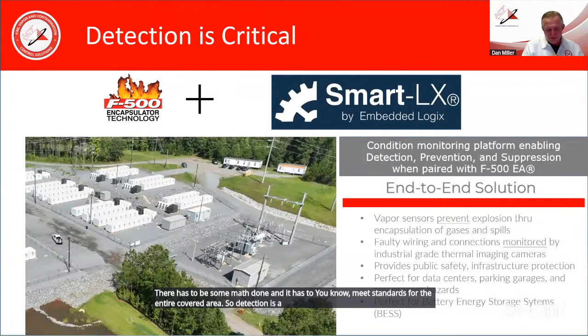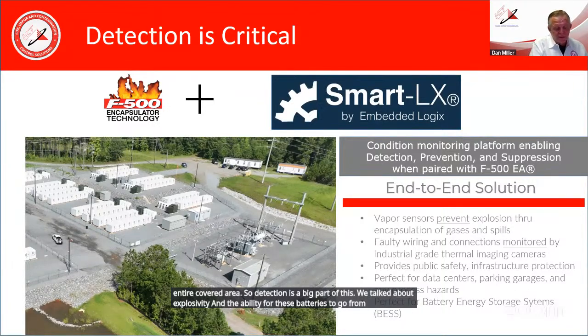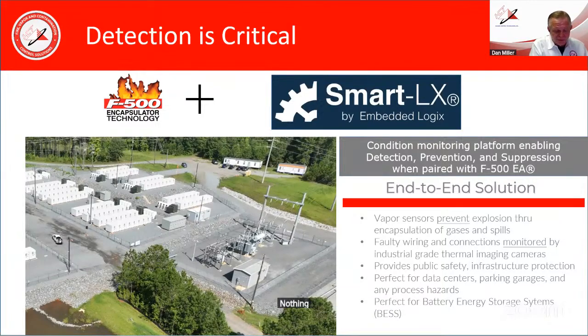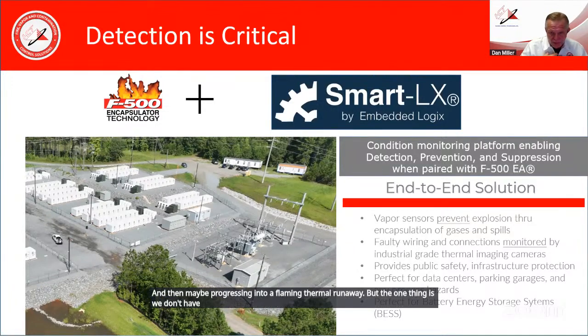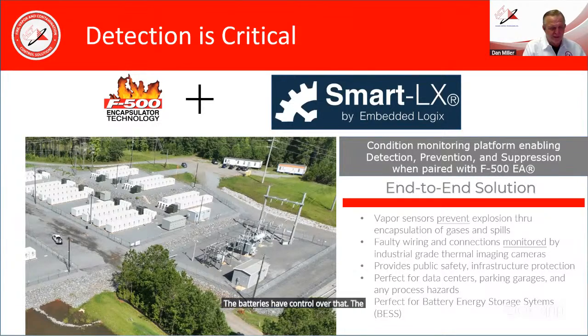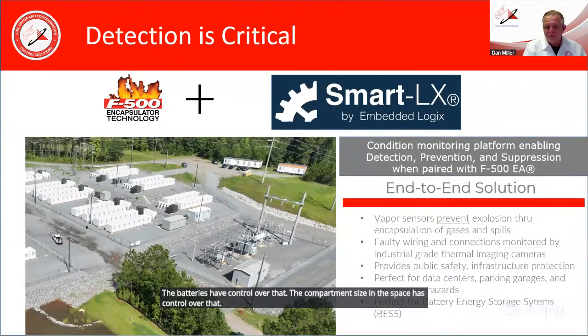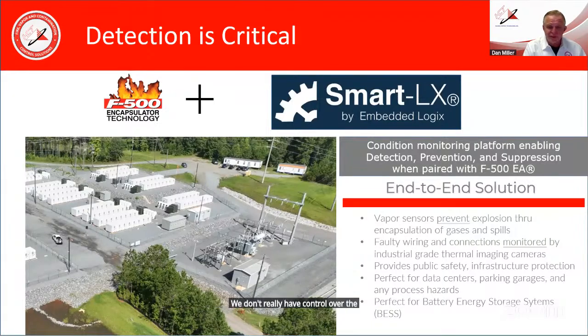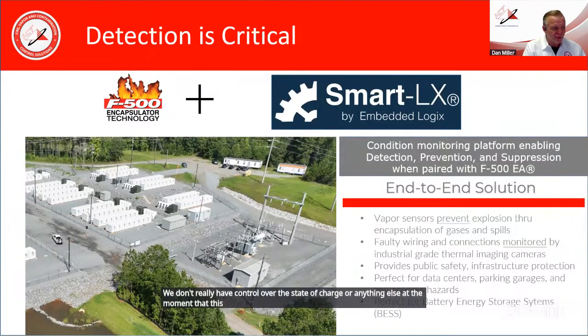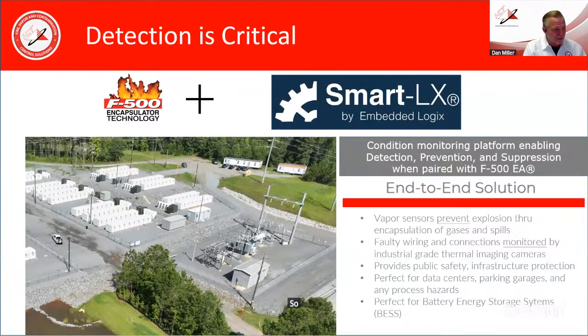We talked about explosivity and the ability for these batteries to go from nothing into a vapor-producing thermal runaway for a period of time, and then maybe progressing into a flaming thermal runaway. But the one thing is, we don't have control over that. No one does. The batteries have control over that, and the compartment size and the space have control over that. We don't really have control over the state of charge or anything else at the moment that this thermal runaway is going to occur. So detection is extremely important.